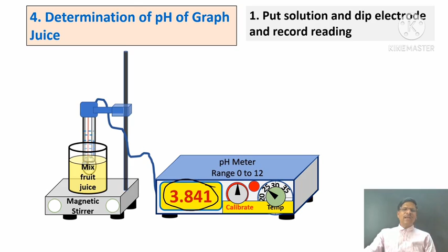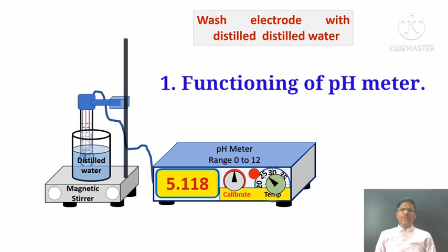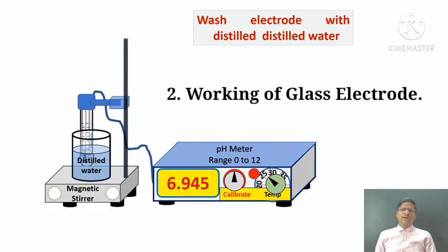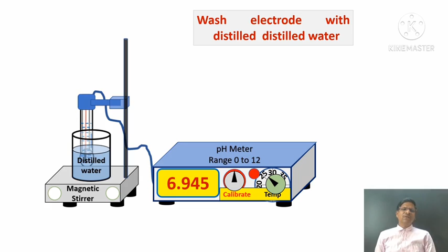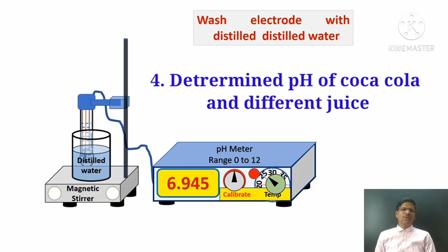So ultimately we have determined the pH of the different juices and they are all acidic in nature, and you have to find out the reason why all these are acidic in nature. The last step, wash with distilled water and keep the electrode in distilled water till the next use. So in this small experiment, we have seen the functioning of the pH meter, we have seen the working of the glass electrode, then we have seen the calibration of the pH meter, and finally we have determined the pH of the cold drinks and the different types of juice.